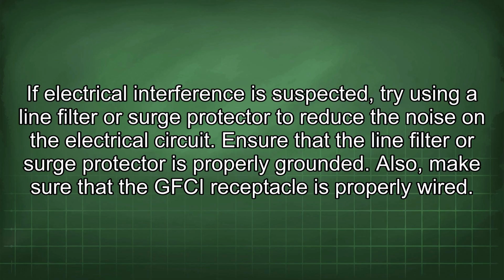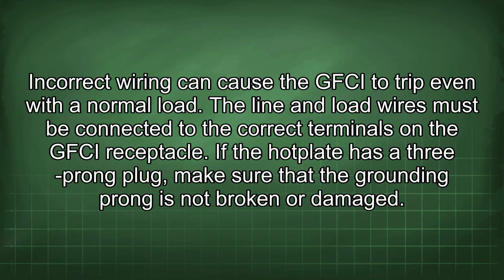If electrical interference is suspected, try using a line filter or surge protector to reduce the noise on the electrical circuit. Ensure that the line filter or surge protector is properly grounded. Also, make sure that the GFCI receptacle is properly wired. Incorrect wiring can cause the GFCI to trip even with a normal load. The line and load wires must be connected to the correct terminals in the GFCI receptacle.